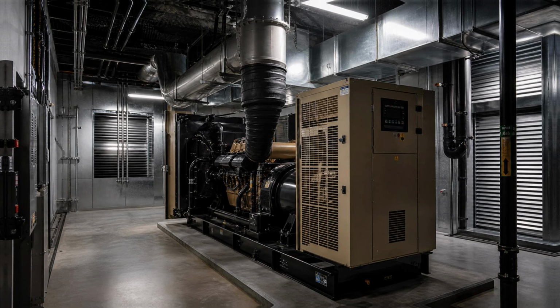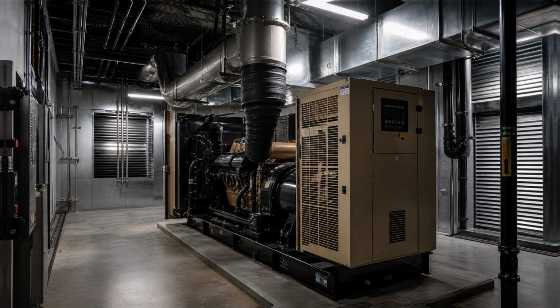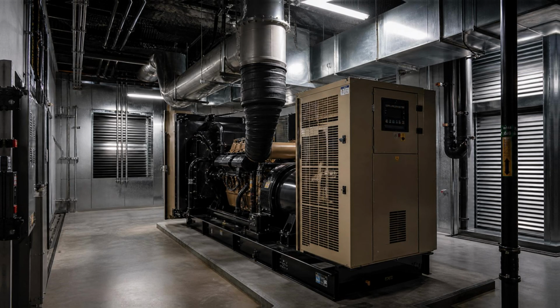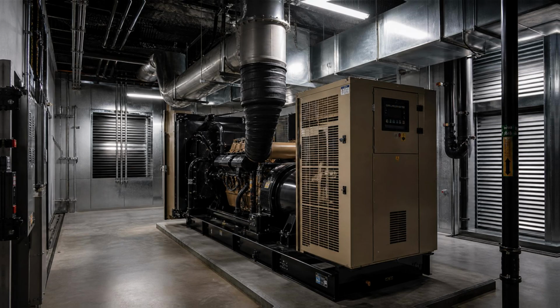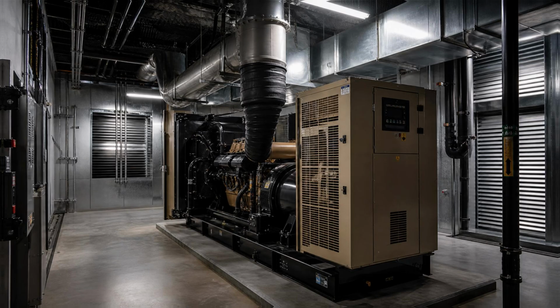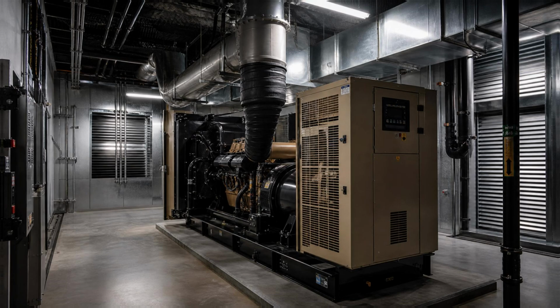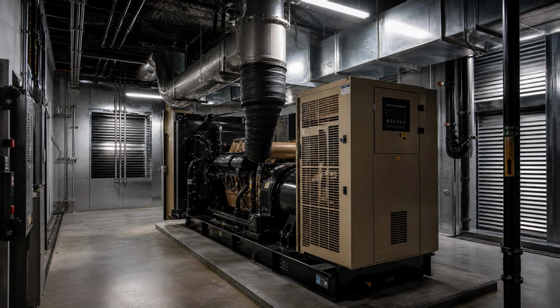The UPS does not announce that its batteries are aging. It does not slow down or flicker or otherwise signal the passage of time. It simply runs, as it always has, while the gradual work of capacity loss proceeds silently inside the battery cabinets. Only the testing reveals what is actually there. Only the maintenance preserves it. And so someone, somewhere on a regular schedule goes to the battery room or the electrical room and performs the quiet work of verification. They check the values, they compare them to the expectations, they make notes, and the system continues, maintained and honest and ready.